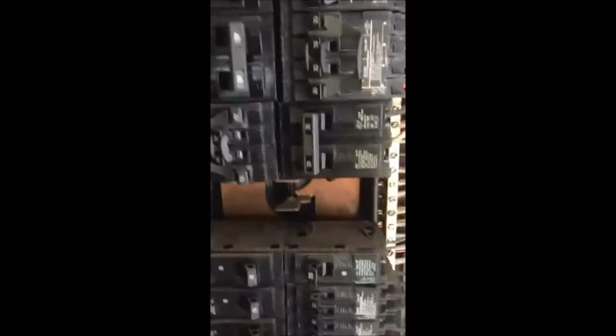We also have another problem with this circuit breaker, and another issue out in the field that we commonly find: this is a 20 amp circuit breaker, and I know it's hard to tell on video, but this is 14 gauge wire attached to a 20 amp circuit breaker. That breaker is oversized for that size wire. It should be a 15 amp circuit breaker for this size wire. 20 amp circuit breakers would typically hold a 12 gauge wire, and that's not what we have here.